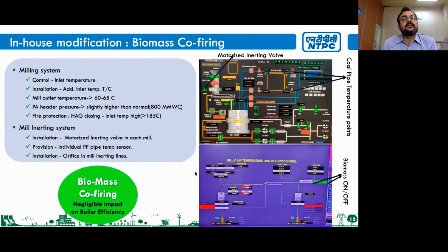Now, talking about the milling system and mill inerting system changes, we have changed our milling system because the biomass flash point is around 200 to 220 degrees Celsius, and we have to keep the mill system temperature below 200, or below 190 degrees Celsius at all times. So we have changed the temperature control to inlet temperature from outlet temperature. And to improve the reliability of the system, we have installed an additional inlet temperature thermocouple in our system. We maintain the mill outlet temperature of 60 to 65 degrees Celsius when we fire biomass in our mills.